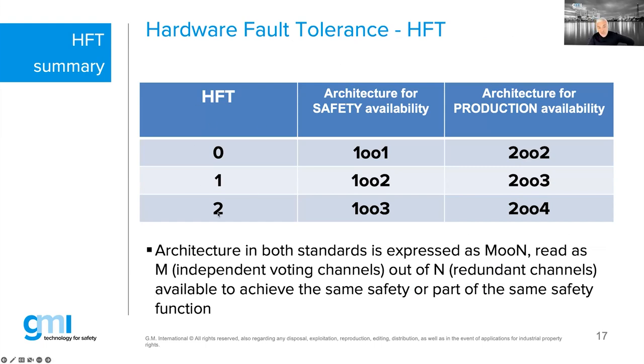HFT of 0 can be built with a 1oo1, but it means no safety redundancy — one dangerous failure and the function cannot go to the safe position. HFT of 1 requires a 1oo2. HFT of 2 requires a 1oo3. If you also want to maintain production availability on top of safety availability, you go to 2oo2, 2oo3, or 2oo4. Architecture in both standards is expressed as MooN — M stands for the independent voting channels, N for the redundant channels available to achieve the safety function.